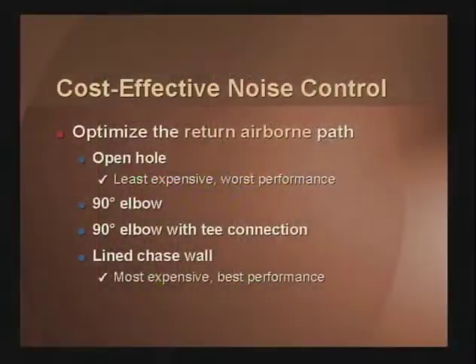What can you do for the return airborne path? Well, there's a couple of alternatives available here. The most popular and easiest to do is simply blow a hole in the mechanical room wall and let the air come into the room. It also has the worst performance in terms of acoustics because all the sound will leak out. You have a 90-degree elbow as a possibility, a 90-degree elbow with a T connection over the occupied space, and finally a lined chase wall, which is the most expensive but offers you the best performance. Let's take a look at each one of these alternatives briefly.